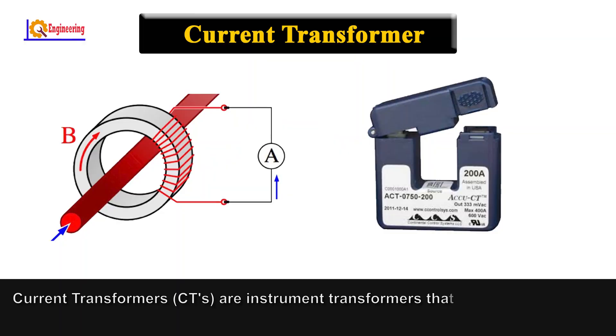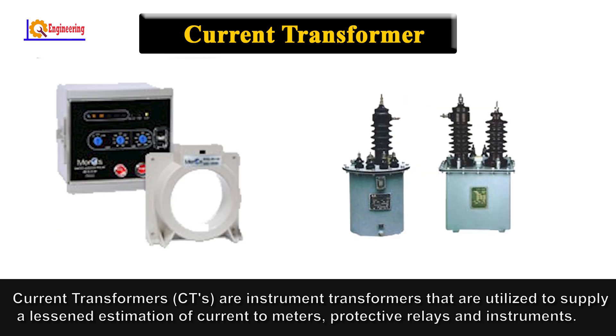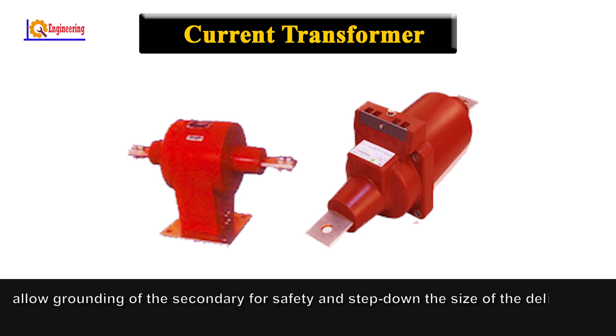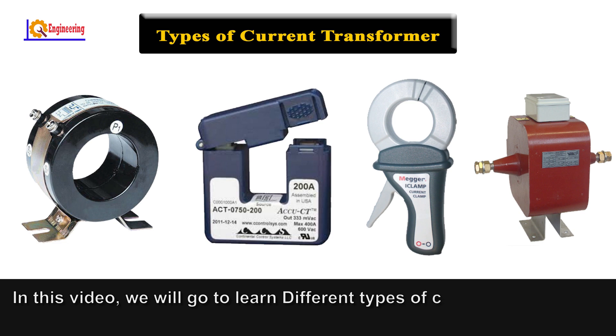Current Transformers (CTs) are instrument transformers utilized to supply a current estimation to meters, protective relays, and instruments. CTs give isolation from the high voltage primary side, allow grounding of the secondary for safety, and step down the delivered current to a value that can be securely handled by the instruments. In this video, we will learn about different types of current transformers.